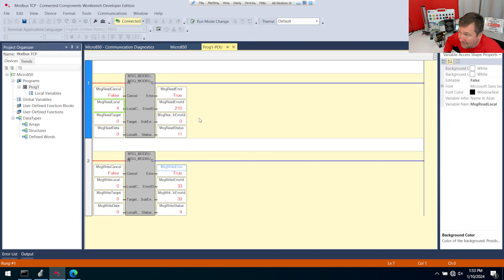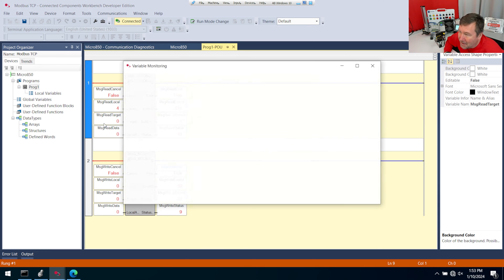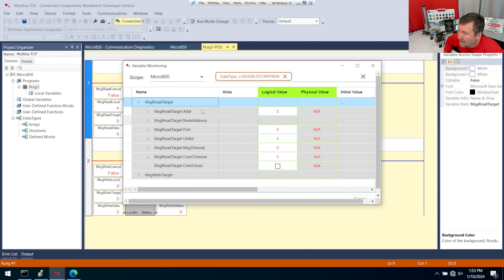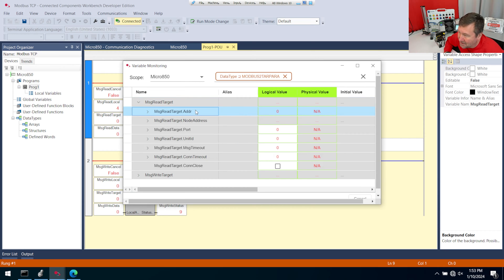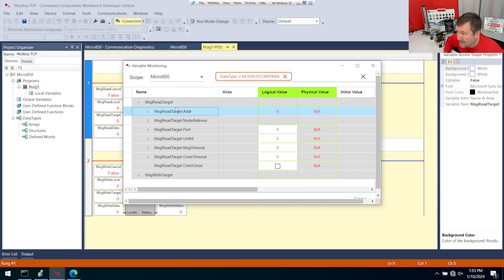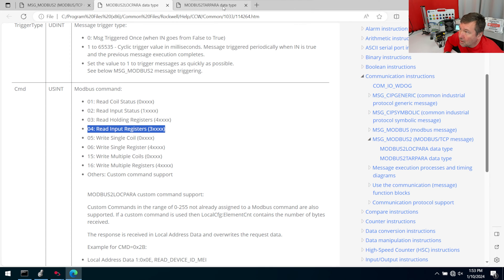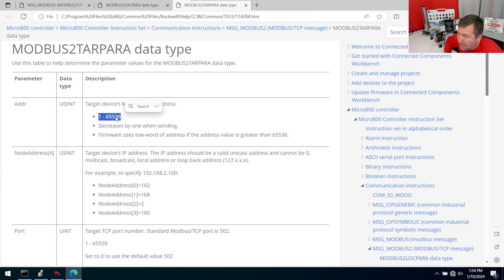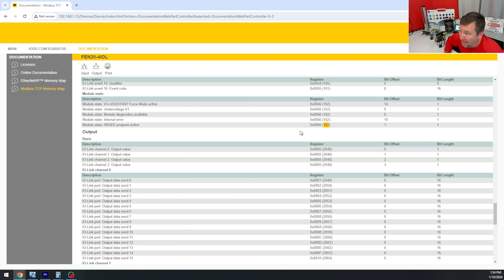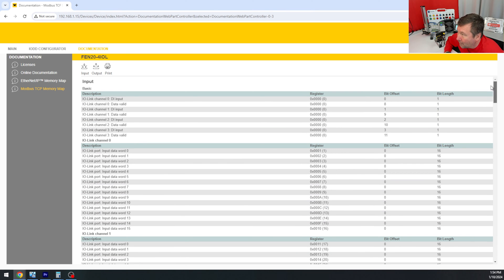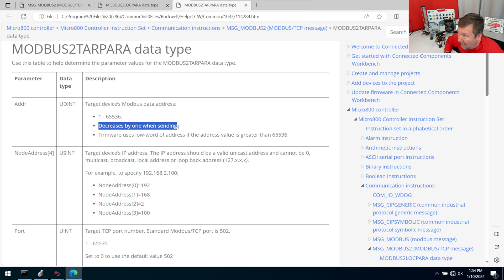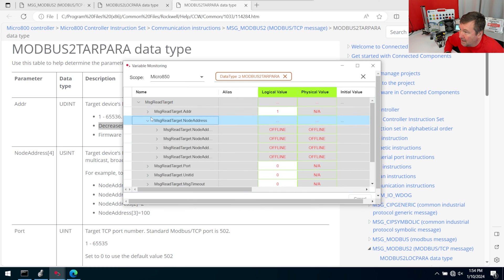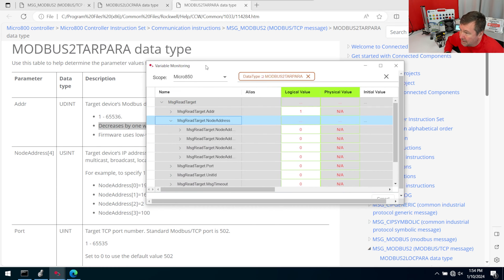So I'm going to make my element count 103. And that did give us a different error. But we're not going to worry about it yet because we still need to configure our target as well. So let's go ahead and open our target up and the message read target. And we need to fill this out as well. Now the one that's going to trip you up a lot of times is actually this first one. It is the address. One, because we have two addresses to deal with. We have an IP address and we have a Modbus address. And this first one is the Modbus address. So we're going to go up to our target parameter tab that we opened up. And here is the trick to it in Connected Components Workbench. The values are 1 through 65,536. And it says it decreases by 1 when sending. Now that is these addresses here. And our first address is 0. But since this says it decreases by 1 when sending, we're actually going to put a 1 in here.